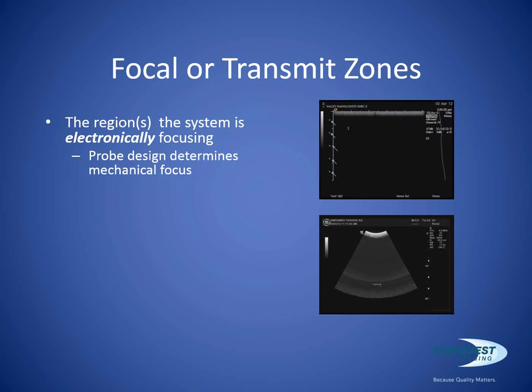Every probe has a sweet spot depending on its design, a certain area where the beam width is the narrowest and the image is what I call the tightest. It's where the highest image quality occurs, and that is due in part to the mechanical design of the probe. But we can also tell the system to electronically focus in other areas of the image outside of the mechanical focus. The system does this through a series of electronic delays within the machine that allow us to adjust the transmit focus.